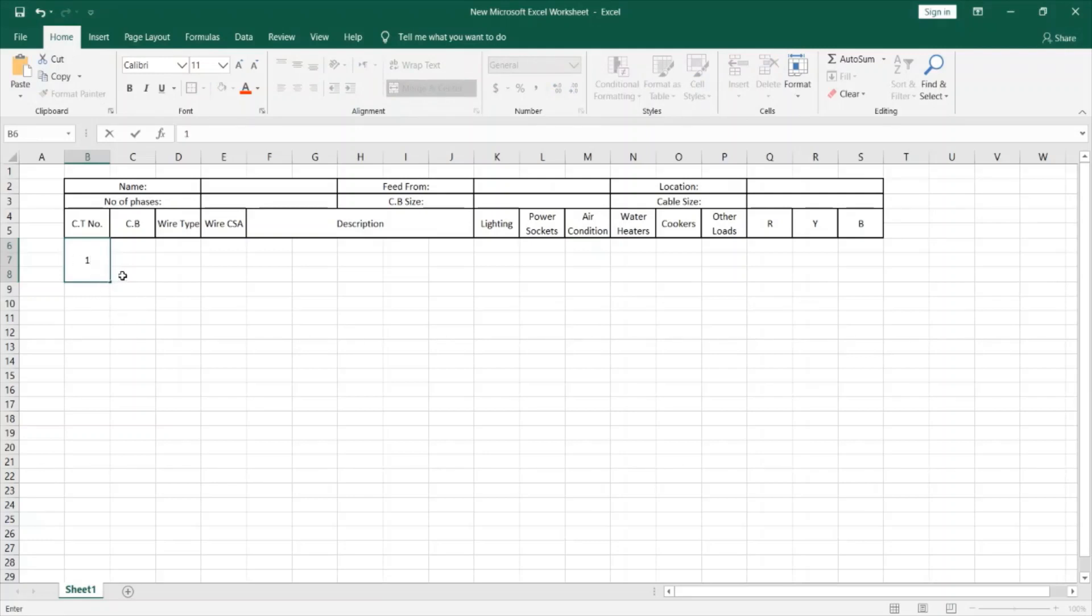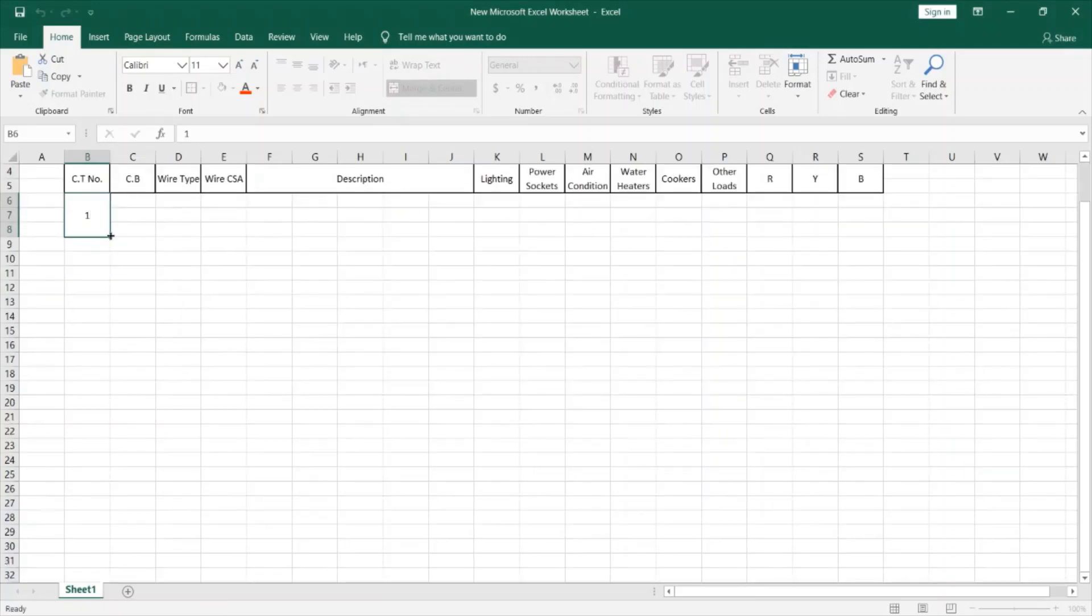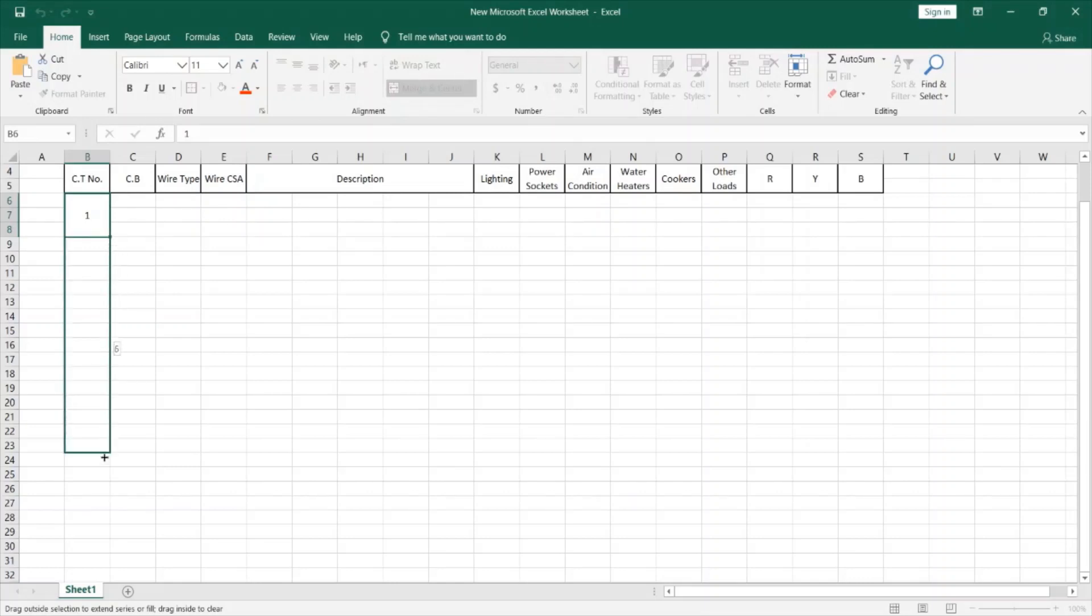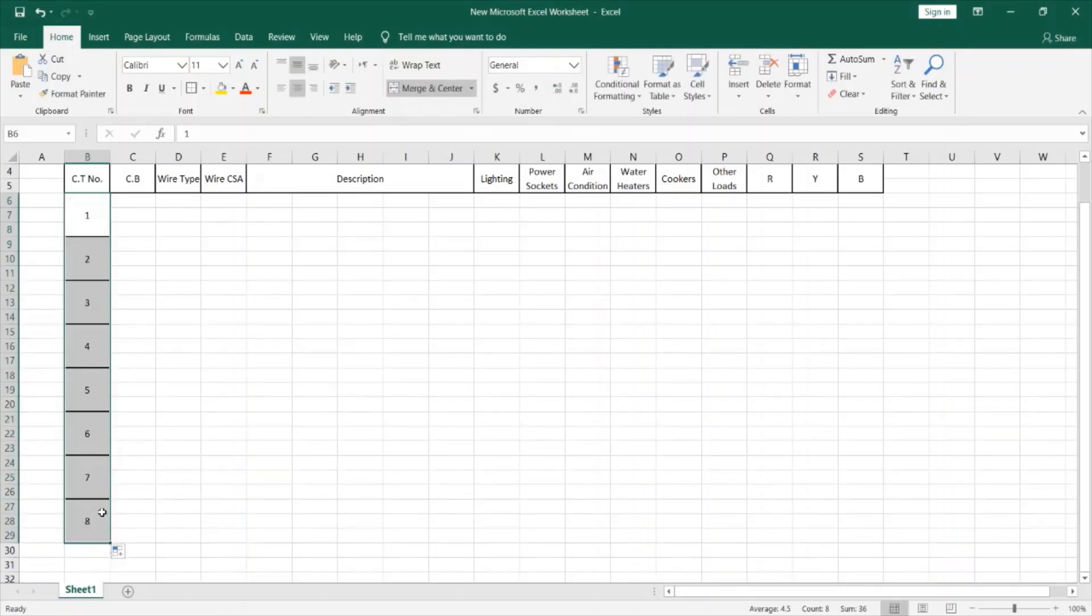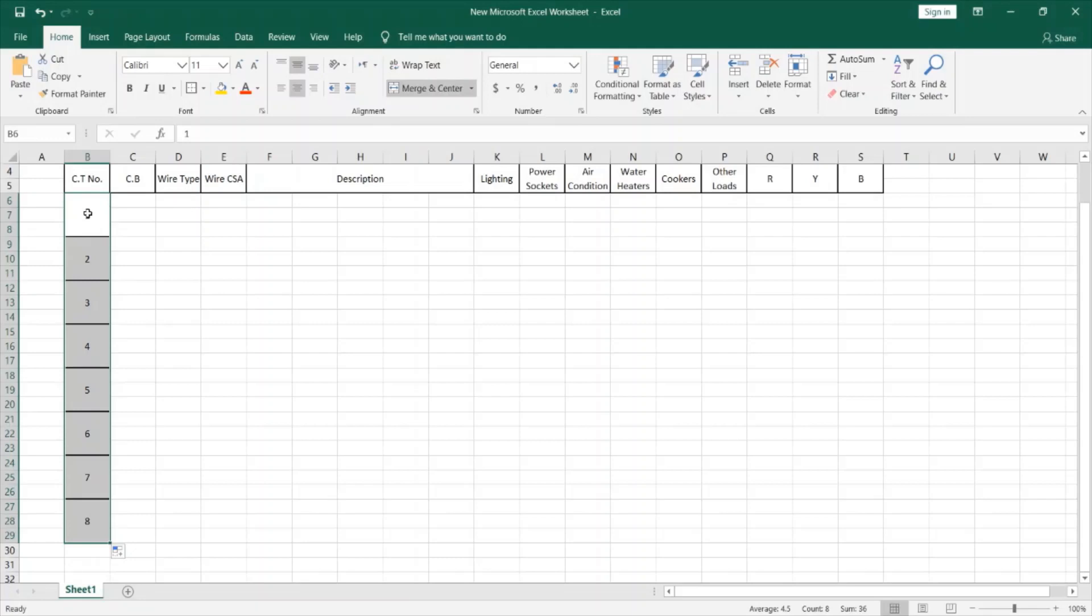So I will assume that this DB is 24 poles. Since each circuit number has three phases, one, two, and three, this means that we will create eight circuit numbers that will give me a total of 24 one phase branch circuits. You will notice that when I define the cell with a number or with number one, then drag it for copy, then the new cells are automatically created with the following numbers.